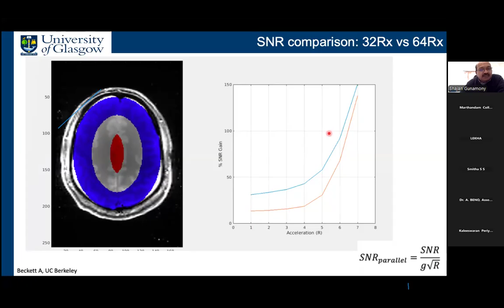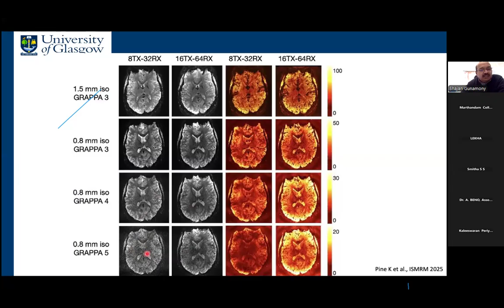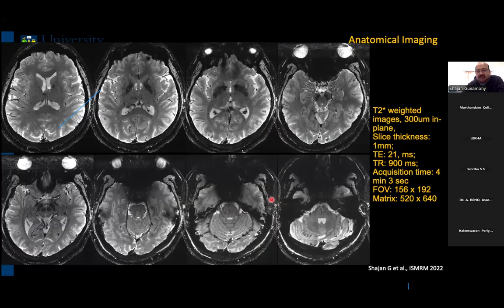So here you can see this gain in a real application. This is 32 versus 64. This is 1.5 millimeter, that's not a very good resolution, and also acceleration factor of 3. You don't see much of a difference here. But if you then increase the resolution to 0.8 millimeter isotropic, and then you increase the acceleration factor to 4, 5, and so on, you really see the difference here. And for example, at 5, you just can't use the 32-channel coil. This is again an image from the Berkeley scanner where we can see the whole brain coverage with nice homogeneity across the slice and very high resolution and so on.